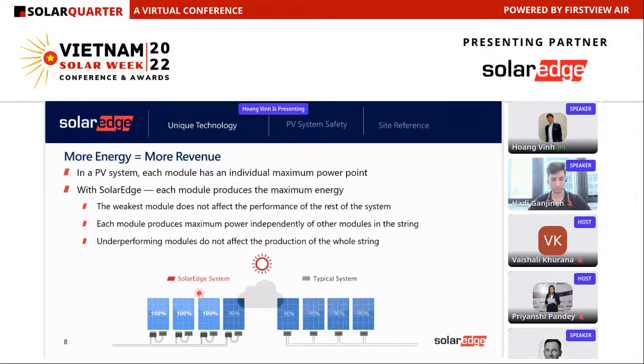For the SolarEdge system, it's totally different. Just one PV drops 90%, the others still operate at the highest operational power they are working at, because here the PV modules are connected with each power optimizer, and the optimizers connect together, meaning in this string the modules don't connect together, they operate separately.